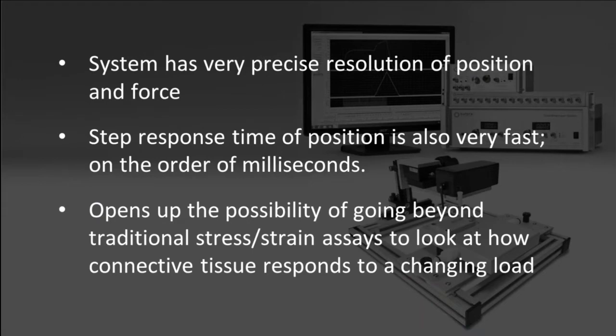So we have lever systems to give you an idea of the specifications we're working with here, which can accommodate tensile loads of up to 100 newtons. At that level, we have an actuation distance greater than 5 centimeters. However, the resolution of all the instruments, the whole family of dual mode levers, is on the order of millinewtons for force and microns for positioning. So quite precise.